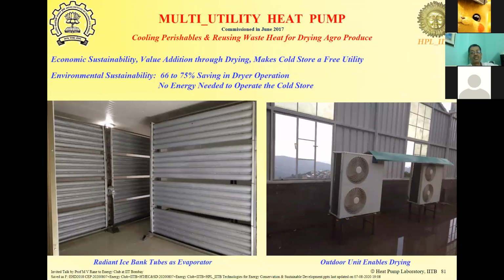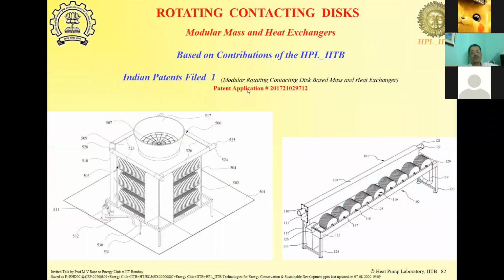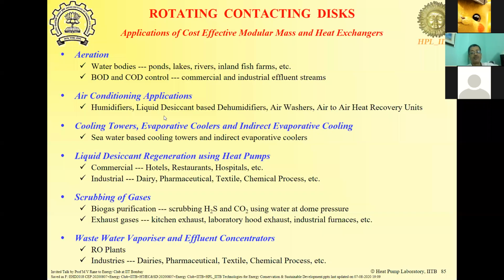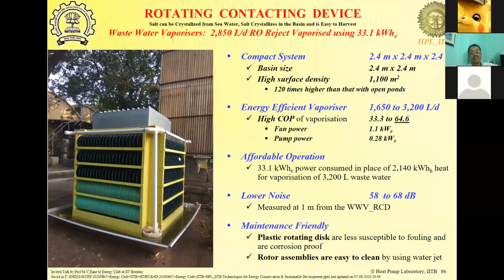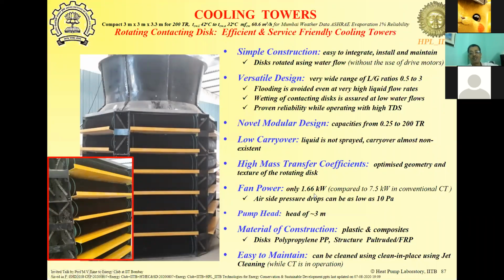Then rotating contacting device. Now the rotating contacting devices are also devices which can be used for air conditioning applications like humidification, liquid desiccant dehumidification, air washers, air-to-air heat recovery, cooling towers, evaporative coolers, indirect evaporative coolers. Okay. I think this is the 200-ton cooling tower we have deployed in the industry. And the beauty of this is that it consumes only, now the latest number is 1.5 kilowatt power consumption compared to the conventional 200-ton consuming 7.5 kilowatts.